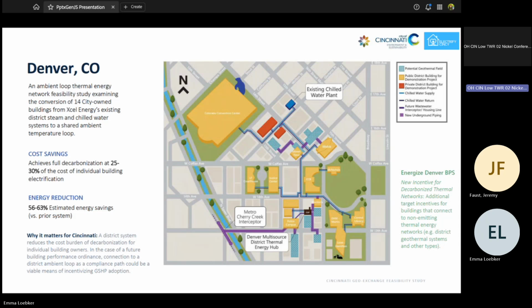What they found is that if they converted the existing chilled water system to a district energy system, they could achieve electrification across the city at 30% of the total cost compared to each building doing it individually—tremendous capital cost savings across the board. They were also able to create an alternative compliance pathway for the building performance standard: rather than just forcing buildings to reduce energy consumption, owners could comply and avoid fines by interconnecting to this future district geo-exchange system. That does one of two things: it helps drive market demand and makes this a more viable solution.